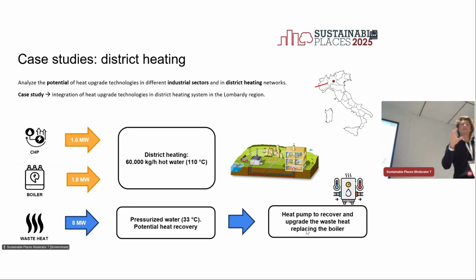But there's a chemical industry close to the district heating which has around 8 megawatts of waste heat in the form of pressurized water at 33 degrees. So the idea is to install a heat pump to recover this heat and replace the gas boiler.